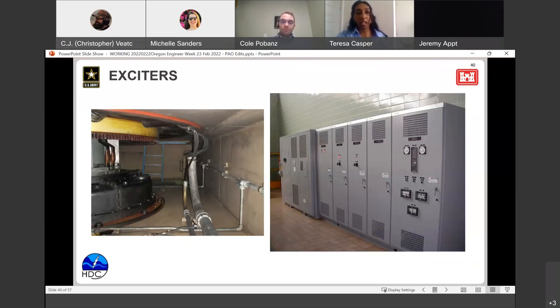Similar to how the governor controls the speed of our generator's spinning, what our exciter does is control the generator's terminal voltage. Similar to governors, the work involved with exciters now is going from our old rotating exciters, shown on the left, to newer digital exciters, shown on the right. The rotating exciters are a lot cooler in terms of how they look and operate, the theory behind it, but going to digital exciters is a lot better for our plants because they're easier to troubleshoot and have fewer points of failure.